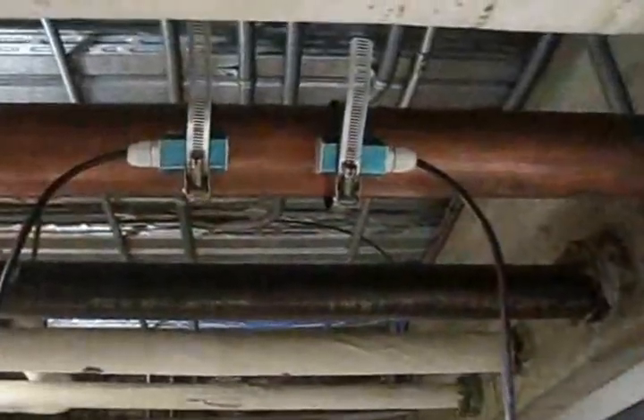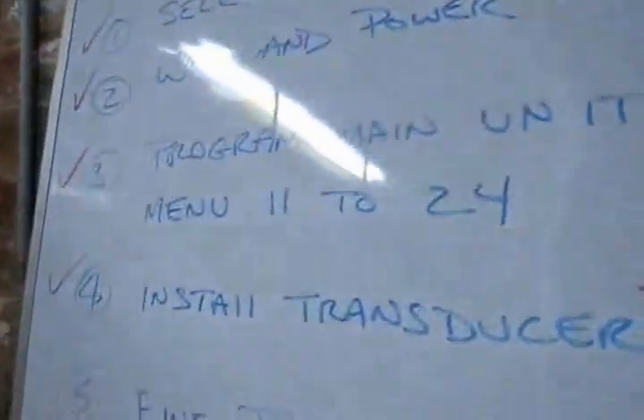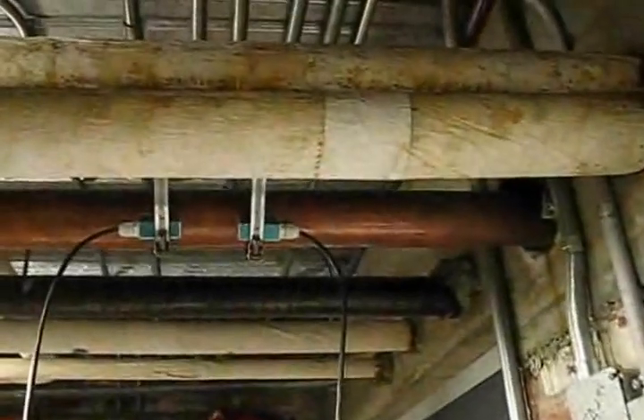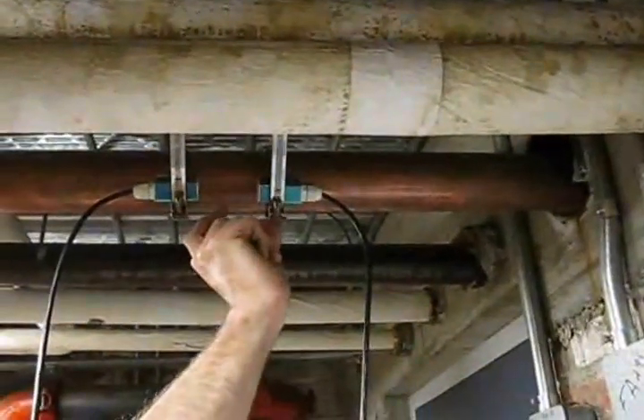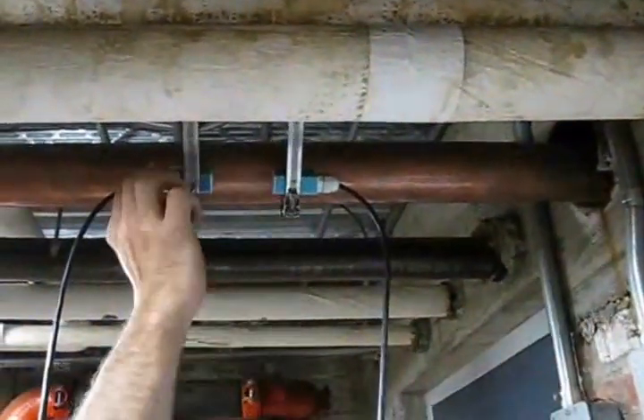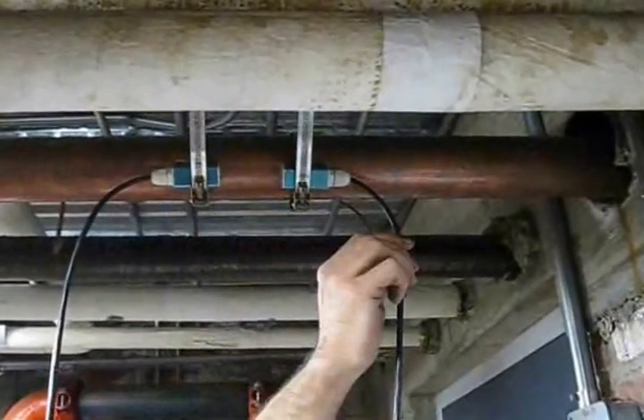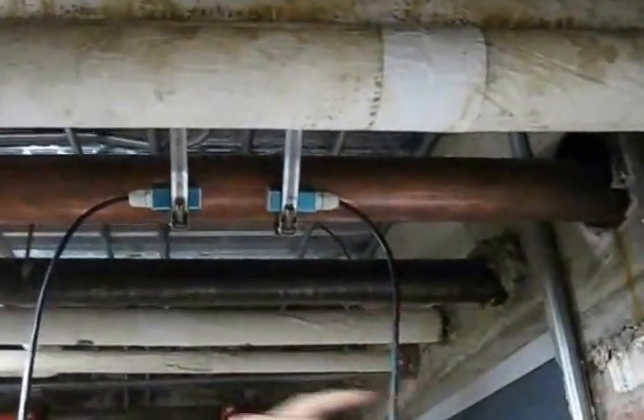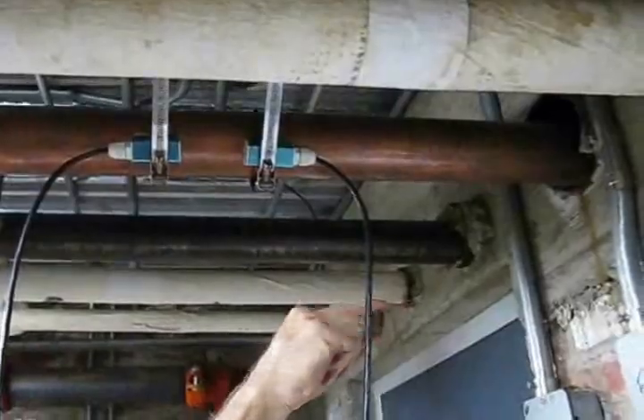Now that we've installed our transducers, we know that the transducers are in line with the pipe. They're placed on the side of the pipe. We have our proper spacing of 2.95. This is the upstream transducer. This is the downstream transducer. We have our water flow going that way.